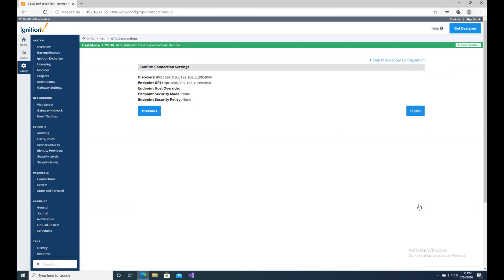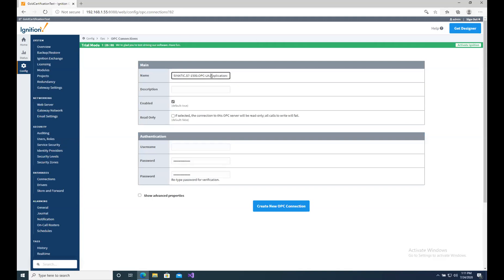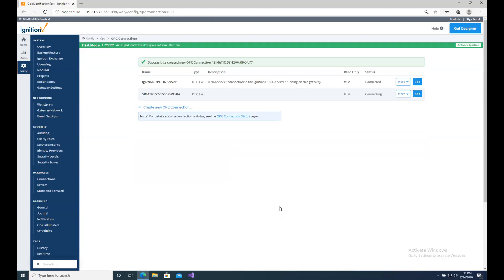I hit next, and currently I don't have security set up on the OPC UA connection, but if I did have a security policy I can enable that, enter credentials, and select the encryption type. For today I'll leave it at the default policy, hit finish, give it a name, and it will start connecting to the OPC UA server. That's how you use the gateway website to do device connections — physically to the device or to the OPC UA server.